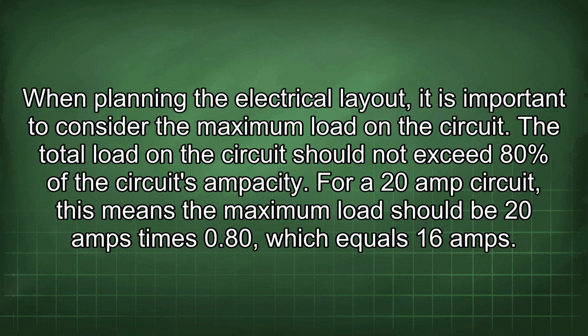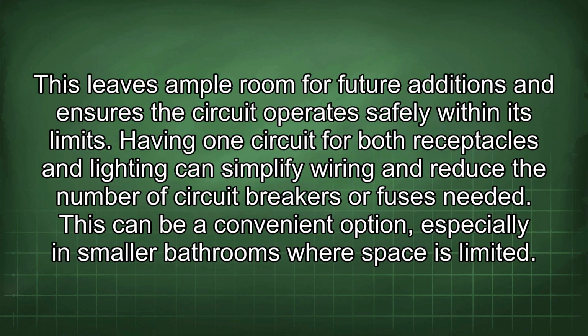When planning the electrical layout, it is important to consider the maximum load in the circuit. The total load in the circuit should not exceed 80% of the circuit capacity. For a 20-amp circuit, this means the maximum load should be 20 amps times 0.80, which equals 16 amps. This leaves ample room for future additions and ensures the circuit operates safely within its limits.